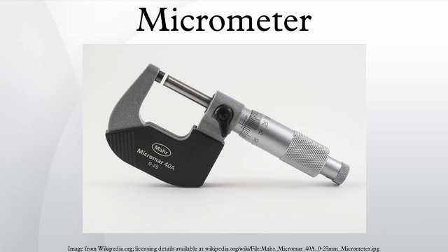As the numbers 1, 2, 3, etc., appear below every fourth subdivision on the frame, indicating hundreds of thousandths, the reading can easily be taken. Suppose the thimble were screwed out so that graduation 2, and 3 additional subdivisions, were visible, and that graduation 1 on the thimble coincided with the axial line on the frame. The reading would then be 0.200 plus 0.075 plus 0.001, or 0.276 inch.